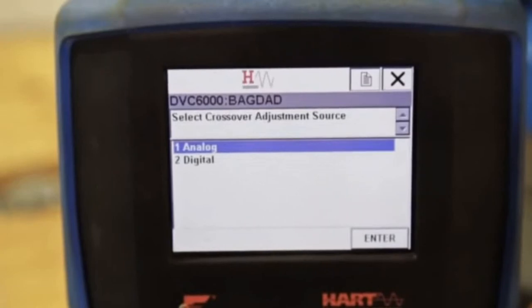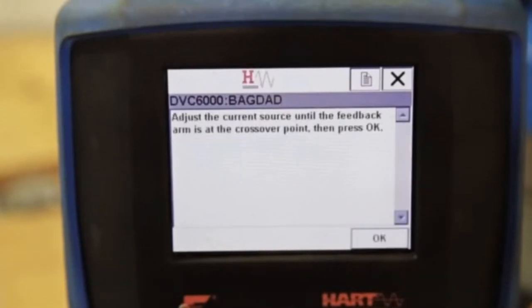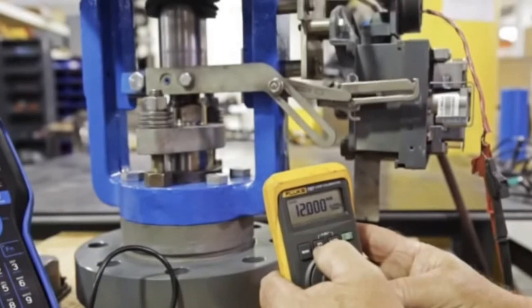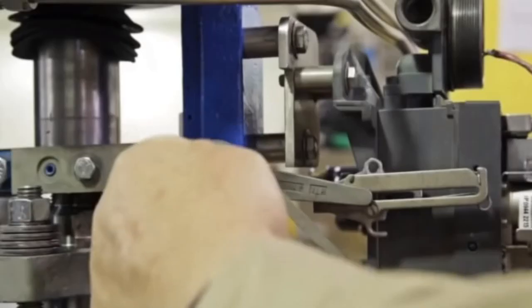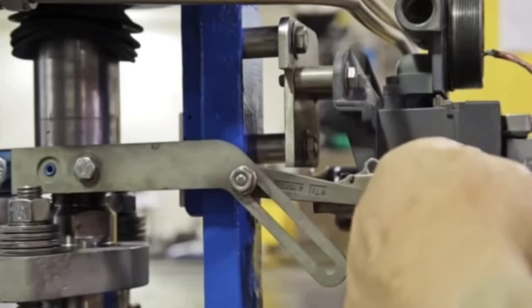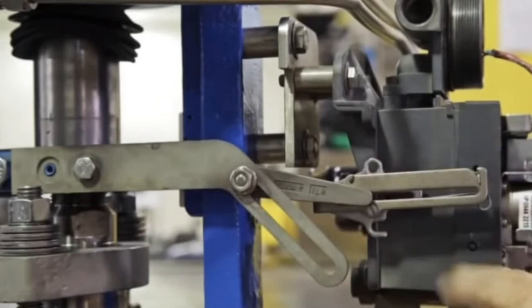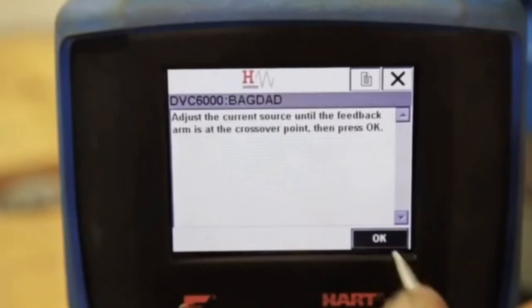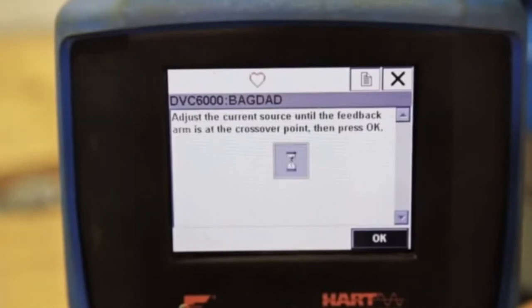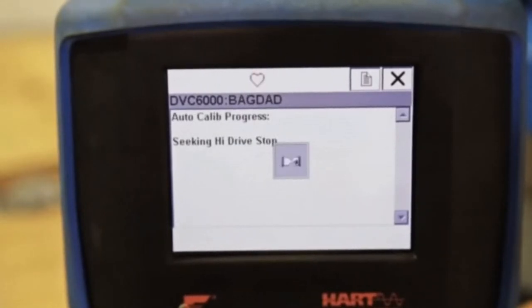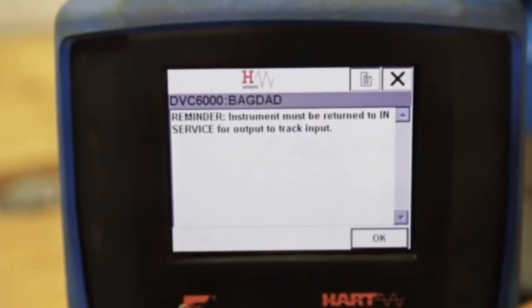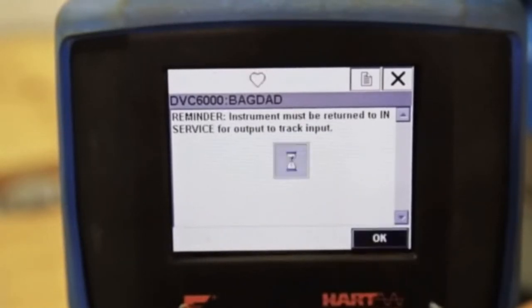Now we will adjust the crossover. We will select Analog for the crossover adjustment source since we are using an analog current source. Using the analog current source, adjust the signal until the feedback arm is 90 degrees in relation to the actuator yoke leg. Select OK once that is complete. The valve will again move to seek the high and low drive stops. The 475 will prompt you to put the positioner back in service for the output to track the input.